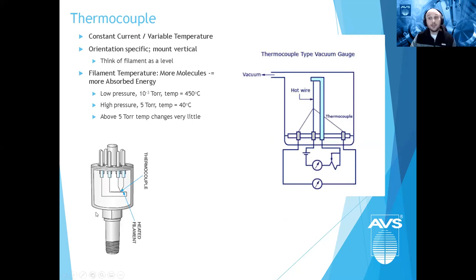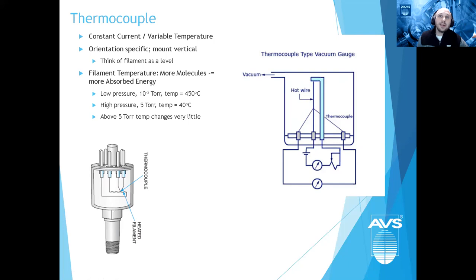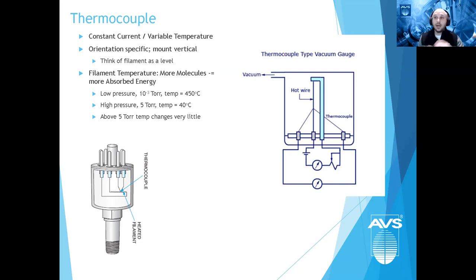For example, with a thermocouple gauge designed to be mounted vertically — so the filament inside is horizontal — if you flip it 90 degrees so the filament is vertical, you could see a reading of 300–400 torr at atmospheric pressure instead of the correct 760 torr. Based on orientation alone, you can significantly skew the measurement from a gas-dependent gauge. Also, at lower pressures with little molecular interaction, the gauge tube gets very hot due to low heat transfer; above about 5 torr, the filament itself is not very hot because of the abundant gas interaction.